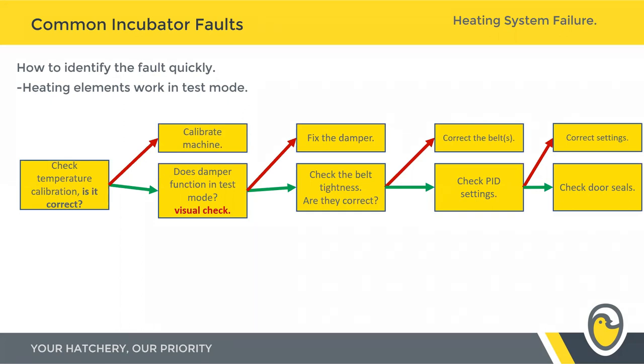If calibration is correct, check whether the damper functions in test mode — visually confirm that all dampers are correctly lined up. Then check the belt tightness: are the fans in the machine physically running at the correct RPM? If not, the usual culprit is belt tightness. Then check the PID settings, which are hidden away inside the control and rarely need changing, but we've had instances where customers went in, changed the settings while testing, and forgot to put them back — which makes one incubator behave very differently from the others.